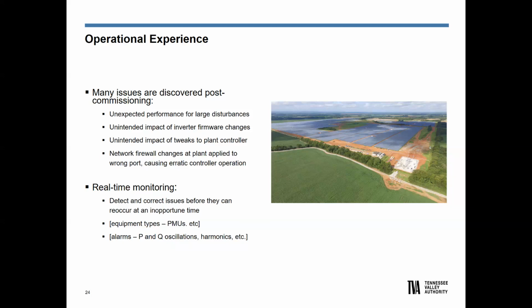We have PMUs and also power quality equipment at each site, so we can detect and correct issues before, a lot of times, the controller or the plant operator can. And we can send them messaging and also ask them to curtail until they fix it because of that. We do have alarming systems both for megawatts and megavars, reactive and real power oscillations, as well as harmonic oscillations. So in summary, from TVA, the last slide, please.